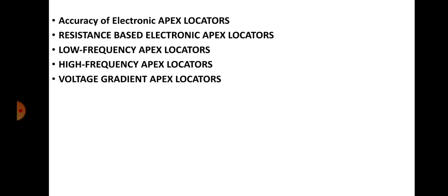The device is able to perform accurate measurements in the presence of electrolytes and pulp tissue due to the file having a special coating except for the exposed tip, thereby decreasing the variable capacitive properties. Accuracy with the Endocater has been reported between 67 and 93.4%.